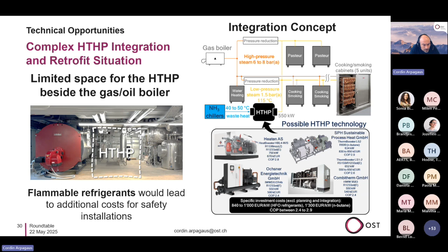Another topic is that today's steam networks are typically generated by steam boilers. They have high pressure, and then with expansion valves, we reduce the pressures to different levels, which are then used at different temperature or pressure levels on site.